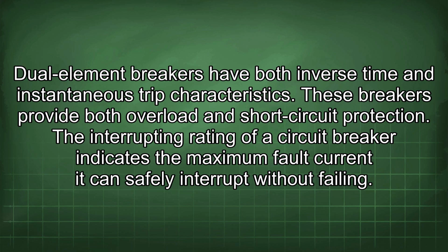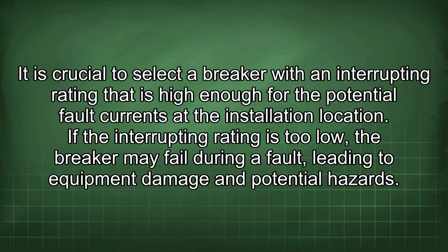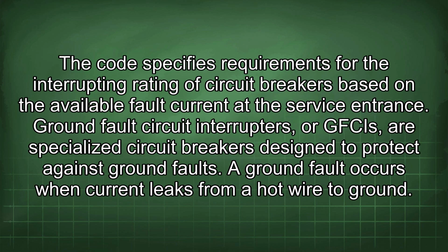The interrupting rating of a circuit breaker indicates the maximum fault current it can safely interrupt without failing. It is crucial to select a breaker with an interrupting rating that is high enough for the potential fault currents at the installation location. If the interrupting rating is too low, the breaker may fail during a fault, leading to equipment damage and potential hazard. The code specifies requirements for the interrupting rating of circuit breakers based on the available fault currents at the service entrance.